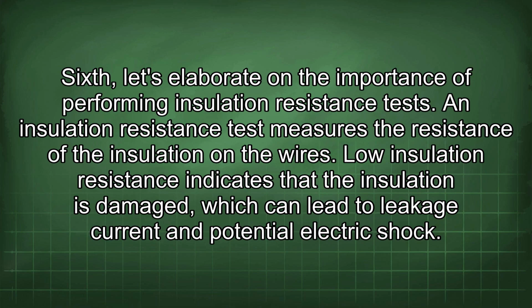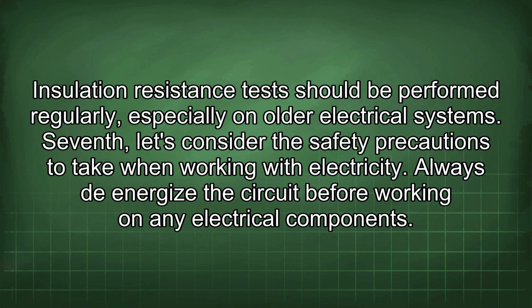Sixth, let's elaborate on the importance of performing insulation resistance tests. An insulation resistance test measures the resistance of the insulation on the wires. Low insulation resistance indicates that the insulation is damaged, which can lead to leakage current and potential electric shock. Insulation resistance tests should be performed regularly, especially on older electrical systems.